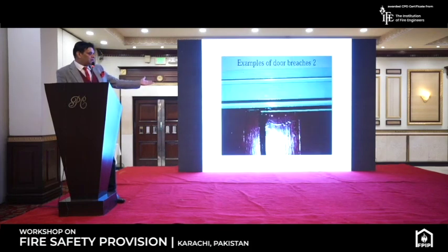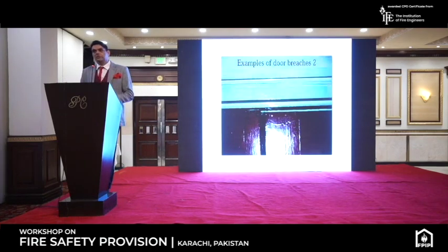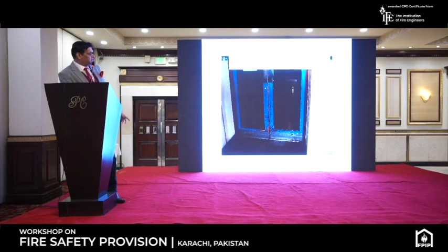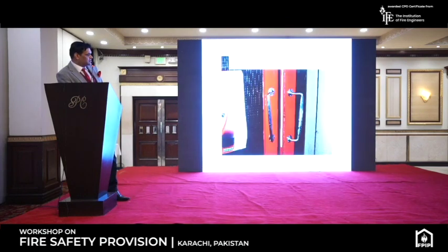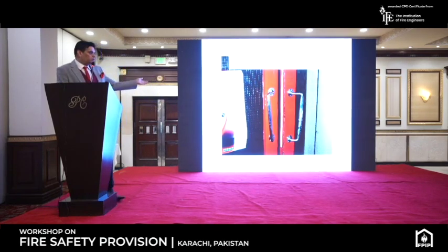Now you can see this kind of violation. Like the door you have, but there is a big gap in it. If the gap is there, it cannot be a fire door, because the route of escape can be compromised. Similarly, this door is there, but there's a big gap in between, which cannot stop the fire, and it's not within compliance. It has to be closed with smoke seals. If the door is always kept open, it will not stop the fire or the smoke. This is one of the breaches we usually see in passive fire protection.